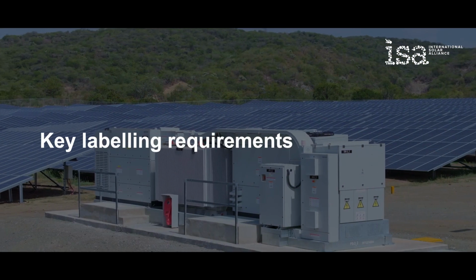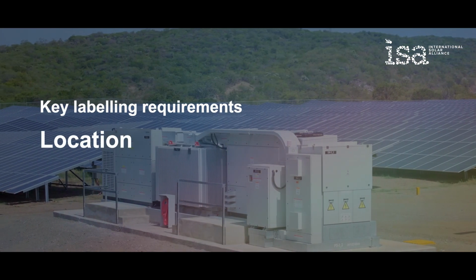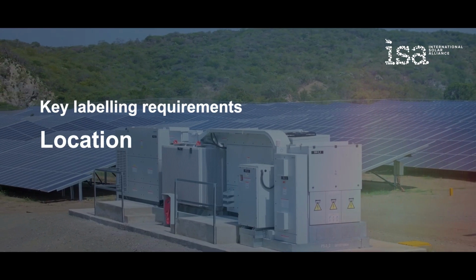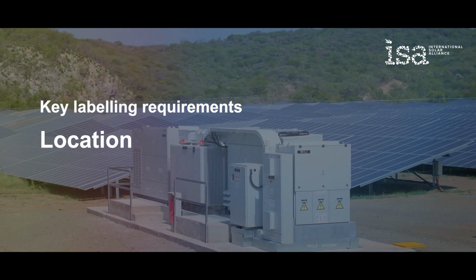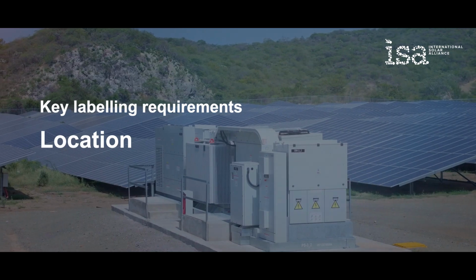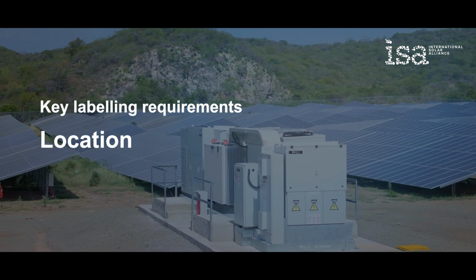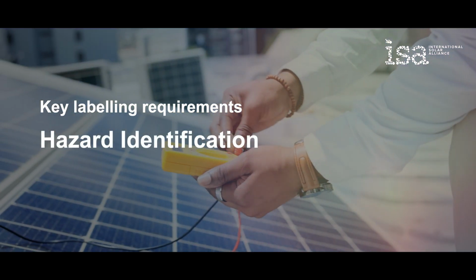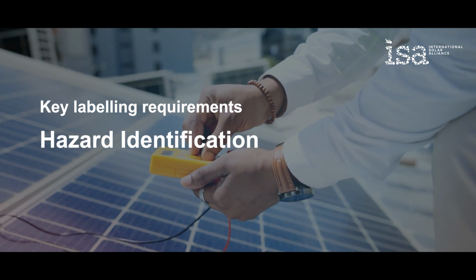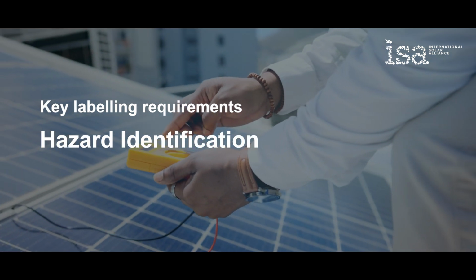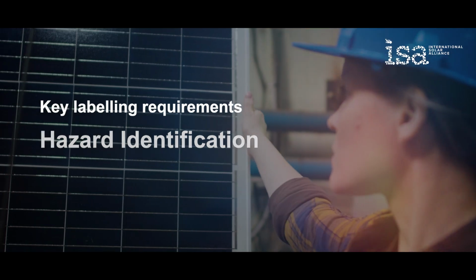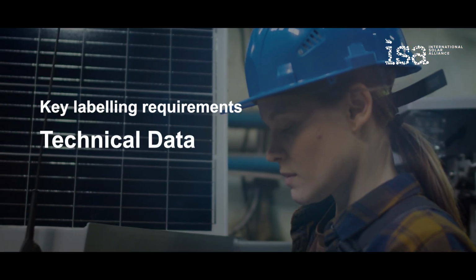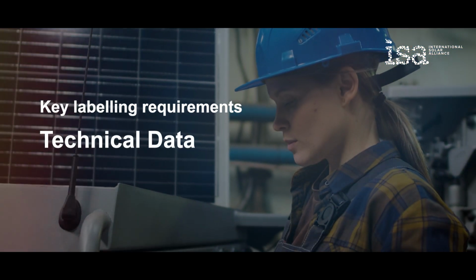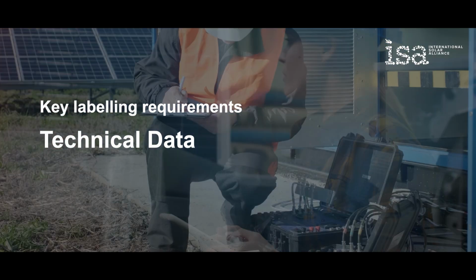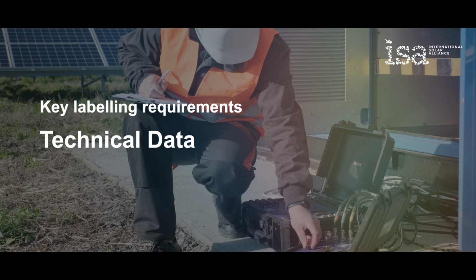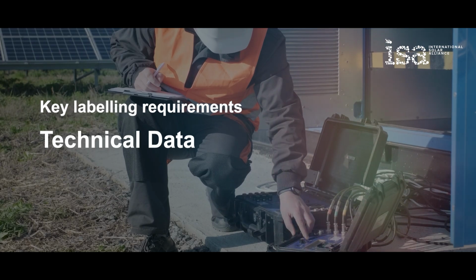Key labeling requirements. Location. Label all points where electrical work may be performed or where a hazard exists. This includes disconnects, AC and DC, junction boxes, combiner boxes, inverters, and other enclosures. Hazard identification. Label all PV power sources with photovoltaic power source and include warning labels for electrical shock hazards. Technical data. Include specific technical information such as maximum system voltage and circuit current, maximum power point voltage and current, AC output operating current and nominal voltage for inverters.